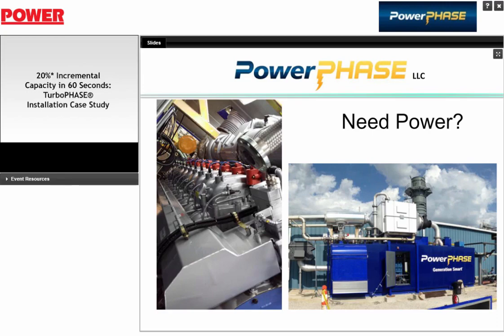Okay. The fuel values that are quoted for consumption and heat rates, are they using HHV or LHV basis? Typically, we talk in LHV when we're talking efficiency, so they're in LHV. Okay. I should point out, too, these first two modules, we're using, I'll call it, a not purpose-built compressor. So this compressor is not nearly as efficient as our production unit. And so if you look at the incremental efficiency of this Turbophase module on that 6-speed plant, we're going to be probably 600 to 800 points lower with our production module that we're building now.